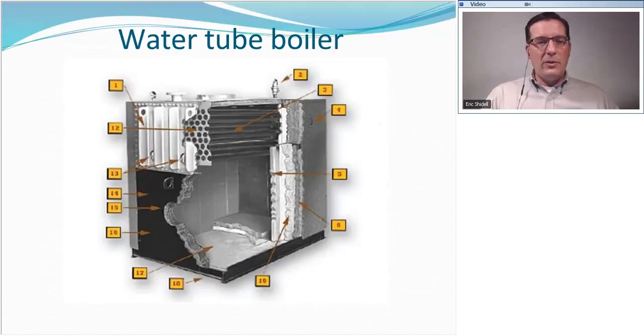The next kind of boiler we're going to talk about is called the water tube boiler. Water tube is just like its name. It has water running through tubes. This is one of the oldest types of boilers ever made. They last forever, and they really consist of a bunch of horizontal tubes with a big old fire below them. These can be fired on gas or they can be fired on oil. Mostly gas. Oil is much less common on these, but they do exist. So you can see down here, big old fire chamber, big old place for burners and flame, and tubes with water running through it. That's all there is to it. Dead simple. They last forever, and they're even repairable.